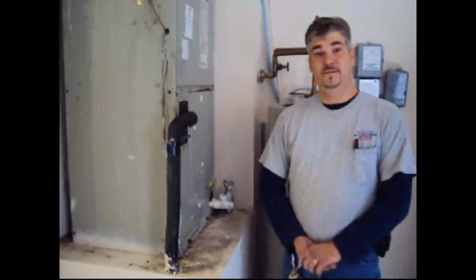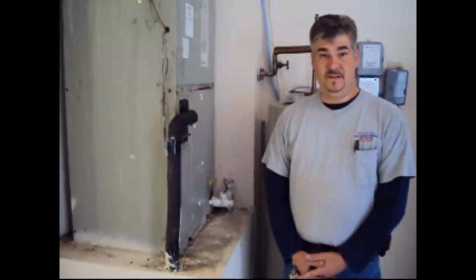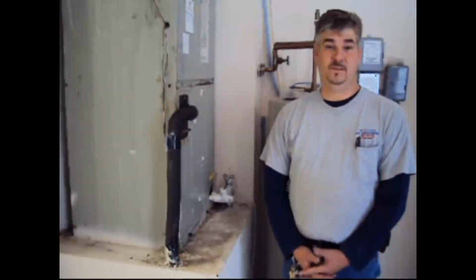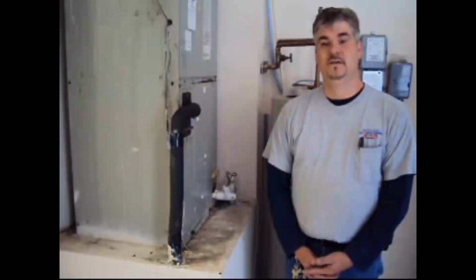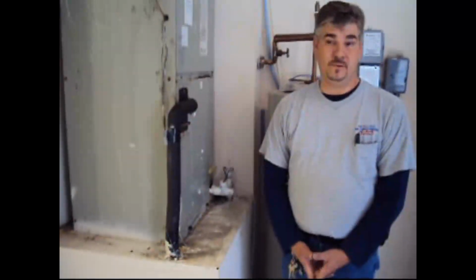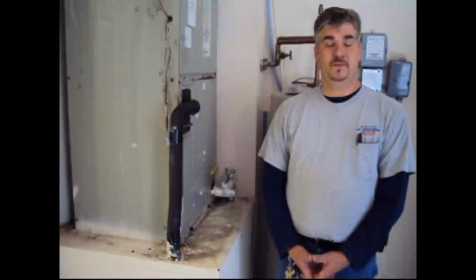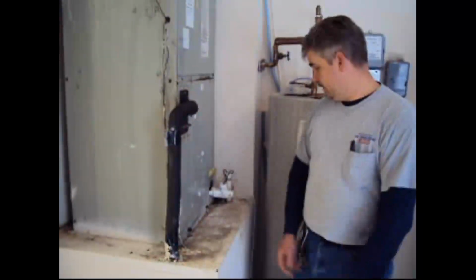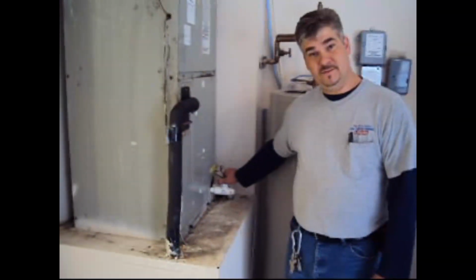Okay. We've verified that our thermostat has good batteries in it. It's set. Our machine has come on and both components have run. We checked to make sure the indoor unit runs, the outdoor unit runs. We checked our circuit breakers to make sure they're not tripped. We also checked our float switch to make sure that it wasn't backed up.